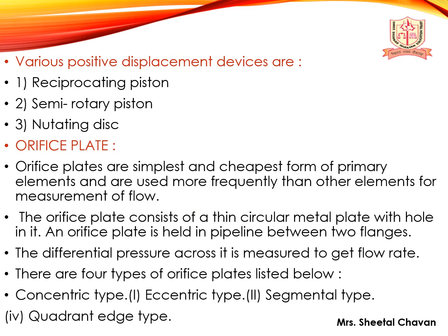Various positive displacement devices are the reciprocating piston, semi-rotary piston, and nutating disc. Orifice plates are the simplest and cheapest form of primary elements and are used more frequently than other elements for flow measurement. An orifice plate consists of a thin circular metal plate with a hole in it, held in a pipeline between two flanges. The differential pressure across it is measured to determine the flow rate.